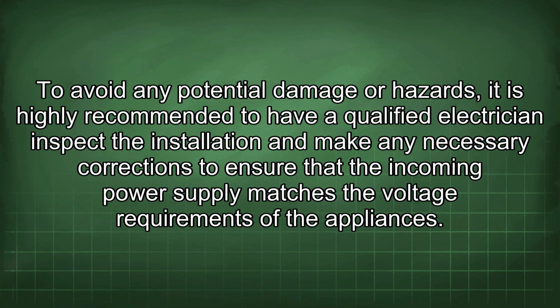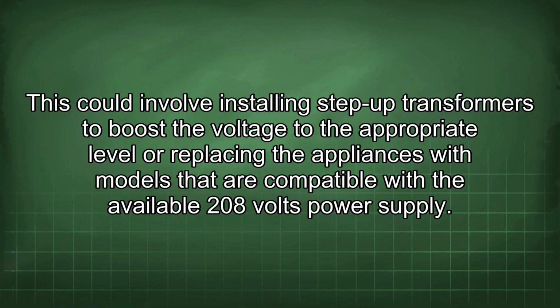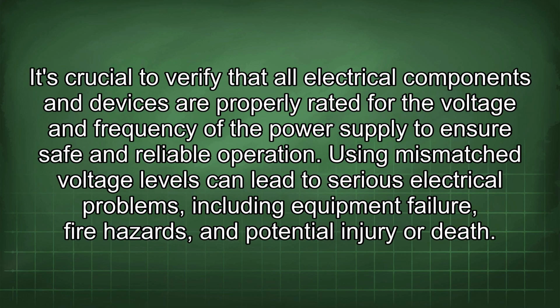To avoid any potential damage or hazards, it is highly recommended to have a qualified electrician inspect the installation and make any necessary corrections to ensure that the incoming power supply matches the voltage requirements of the appliances. This could involve installing step-up transformers to boost the voltage to the appropriate level or replacing the appliances with models that are compatible with the available 208 volts power supply. It's crucial to verify that all electrical components and devices are properly rated for the voltage and frequency of the power supply to ensure safe and reliable operation.